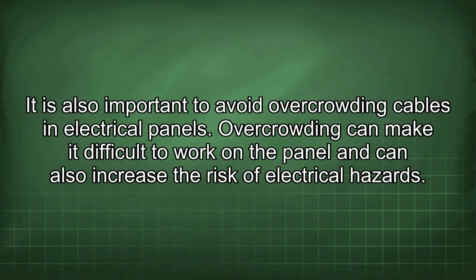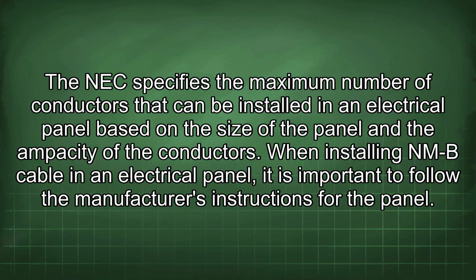It is also important to avoid overcrowding cables in electrical panels. Overcrowding can make it difficult to work on the panel and can also increase the risk of electrical hazards. The NEC specifies a maximum number of conductors that can be installed in an electrical panel based on the size of the panel and the ampacity of the conductors.